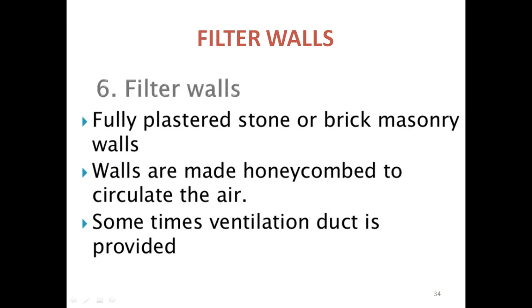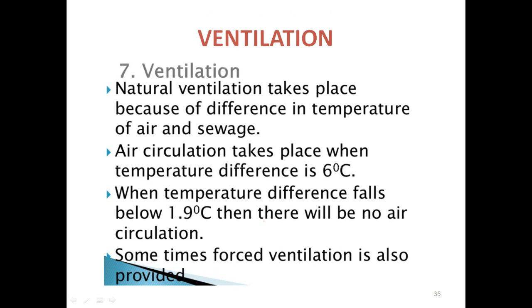Now the filter walls. Fully plastered stone or brick masonry walls are there. Walls are made honeycomb to circulate the air. Sometimes ventilation duct is also provided. Now ventilation. Natural ventilation takes place because of difference in temperature of air and sewage. Naturally, when it is open to air, there is a difference in temperature, and due to this, the natural ventilation takes place. Air circulation takes place when temperature difference is 6 degree Celsius. When temperature difference falls below 1.9 degree Celsius, then there will be no air circulation. Sometimes forced ventilation is also provided.